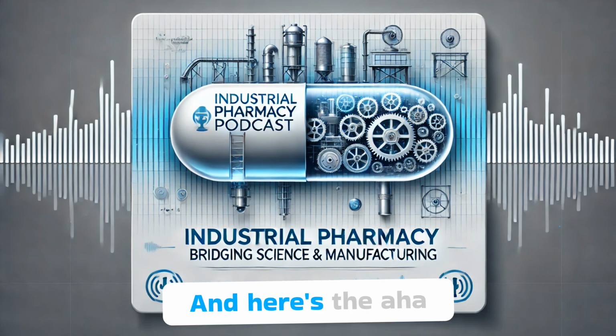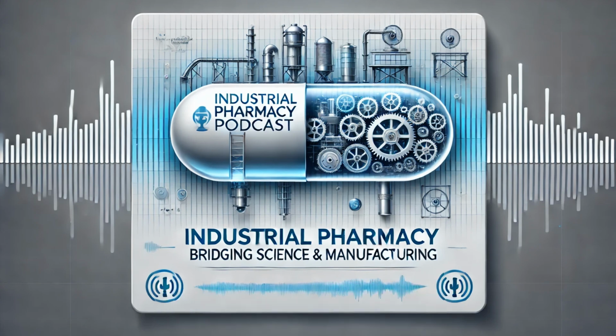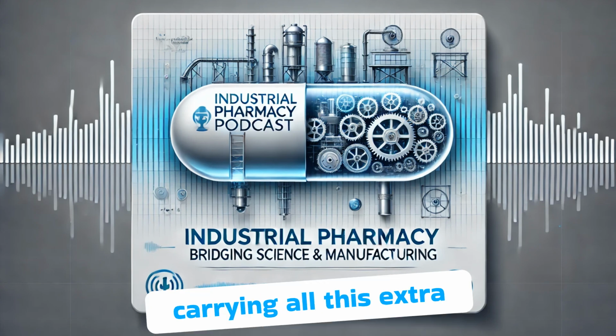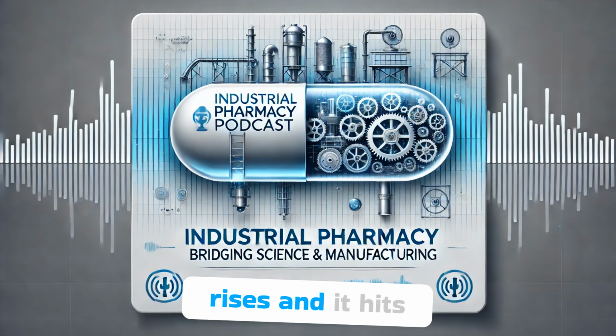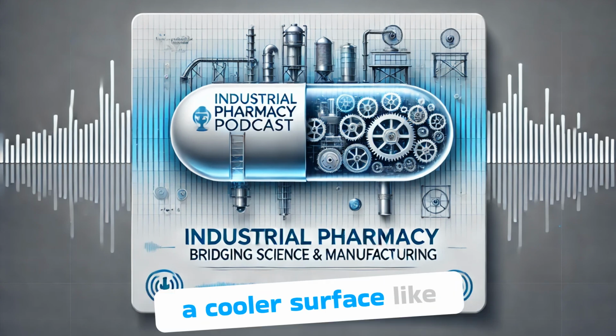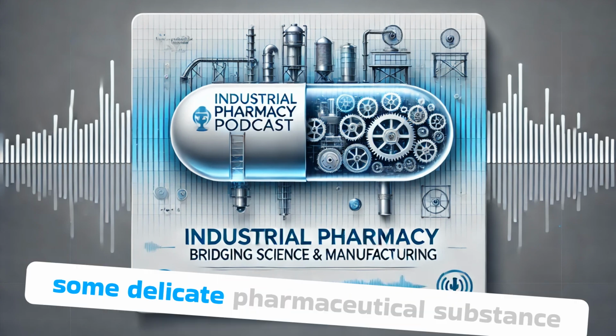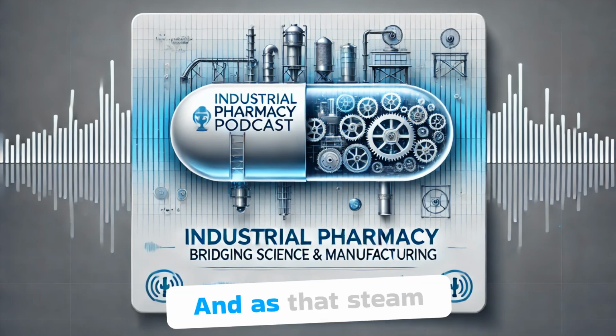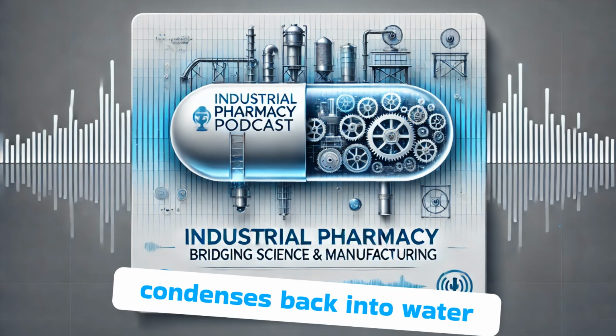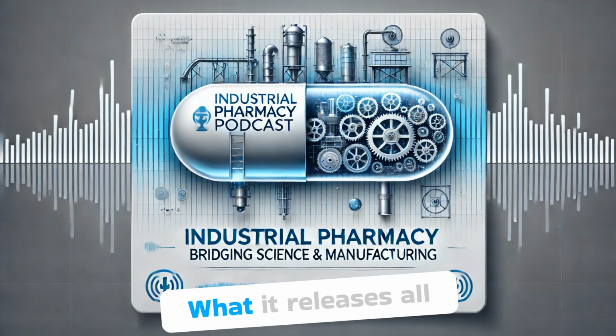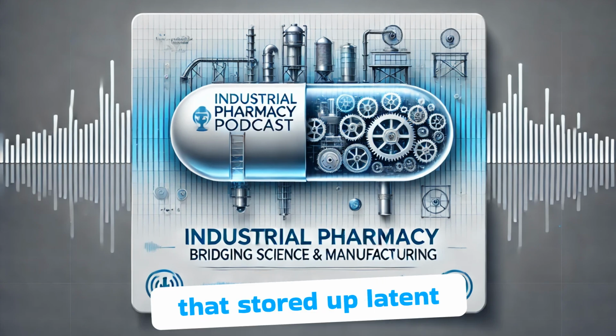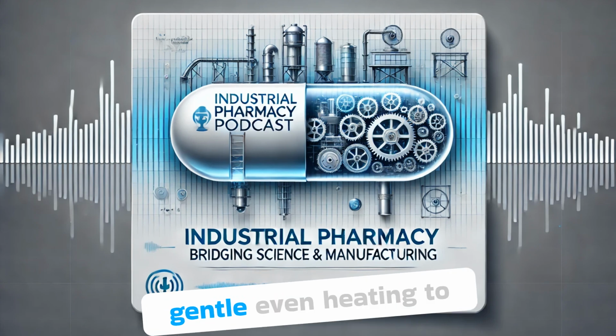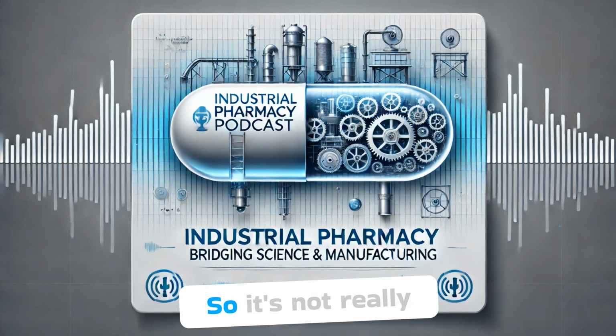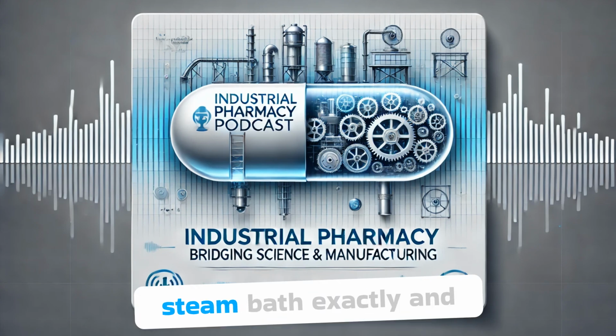Exactly. And here's the aha moment. That steam is now carrying all this extra energy, that latent heat, rises, and hits a cooler surface, like, say, a dish with some delicate pharmaceutical substance in it. And as that steam condenses back into water on that cooler surface, guess what? What? It releases all that stored up latent heat, and that provides gentle, even heating to whatever's in that dish. So it's not really a water bath. It's more like a steam bath.